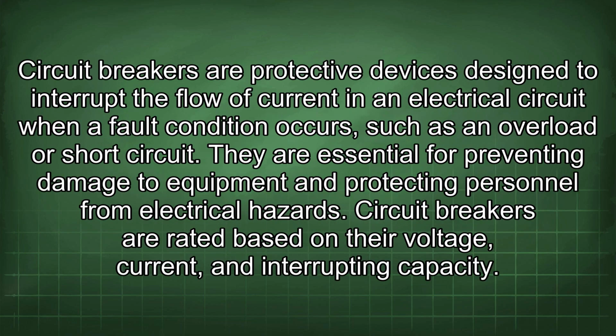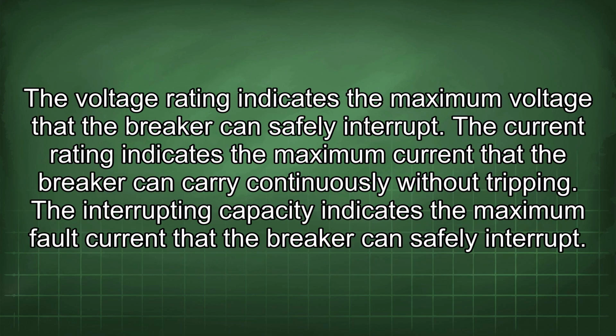Circuit breakers are protective devices designed to interrupt the flow of current in an electrical circuit when a fault condition occurs, such as an overload or short circuit. They are essential for preventing damage to equipment and protecting personnel from electrical hazards. Circuit breakers are rated based on their voltage, current, and interrupting capacity. The voltage rating indicates the maximum voltage that the breaker can safely interrupt. The current rating indicates the maximum current that the breaker can carry continuously without tripping. The interrupting capacity indicates the maximum fault current that the breaker can safely interrupt.